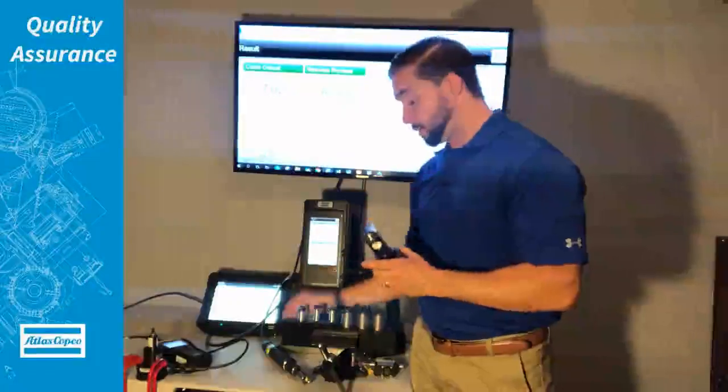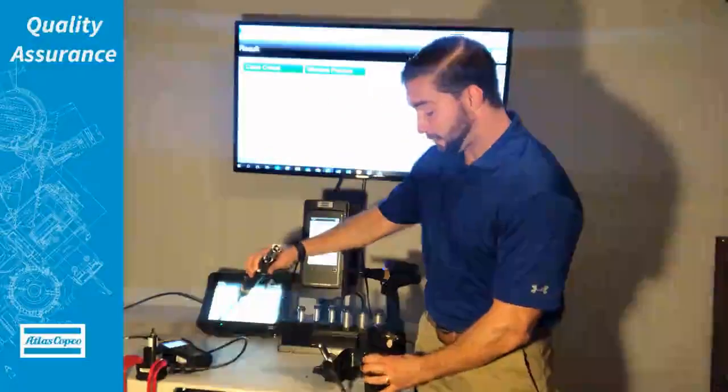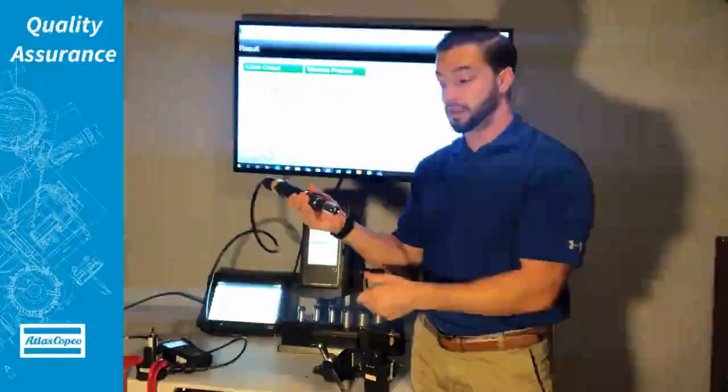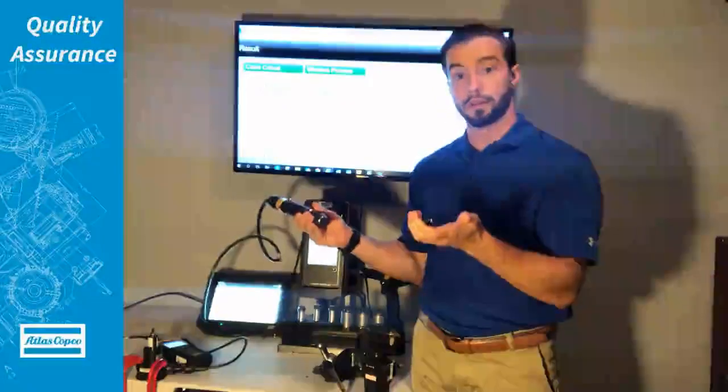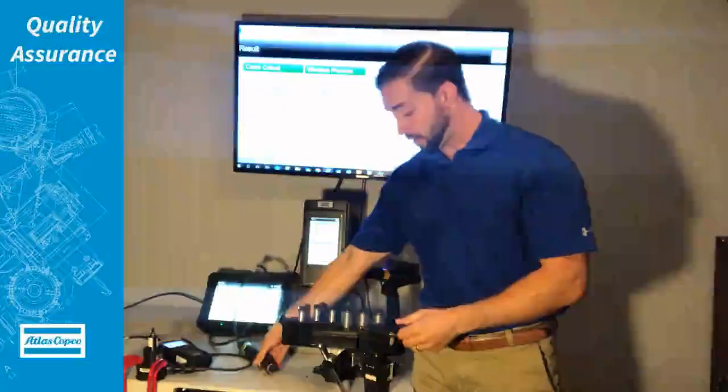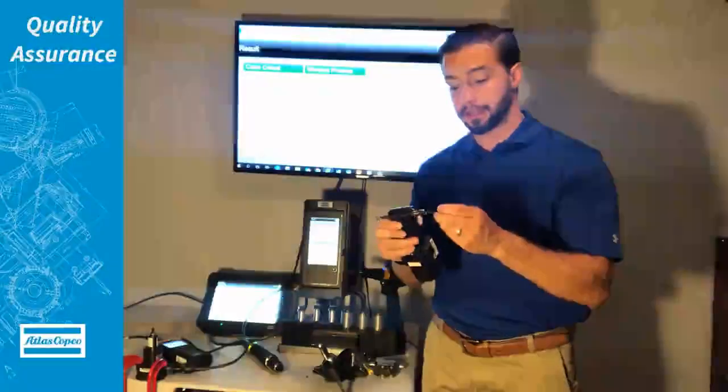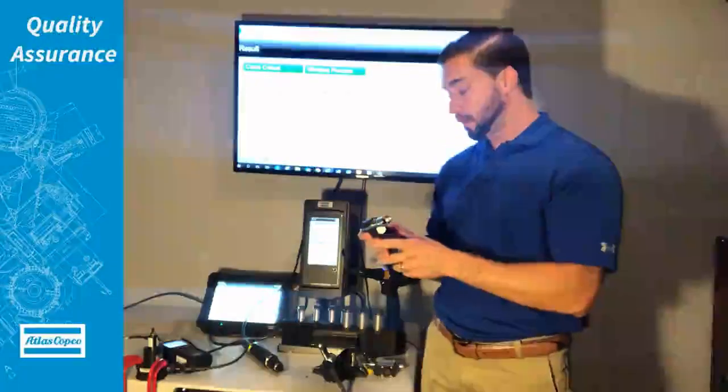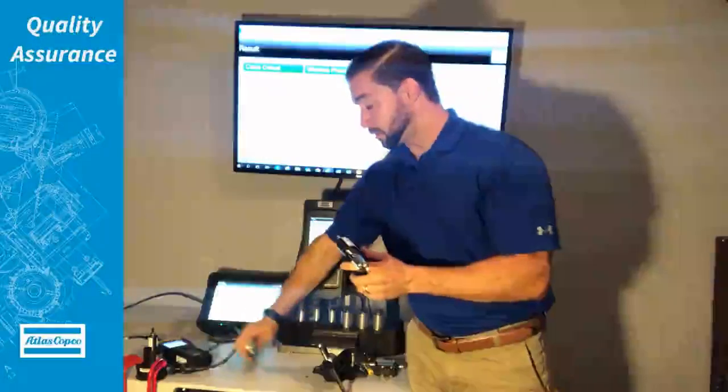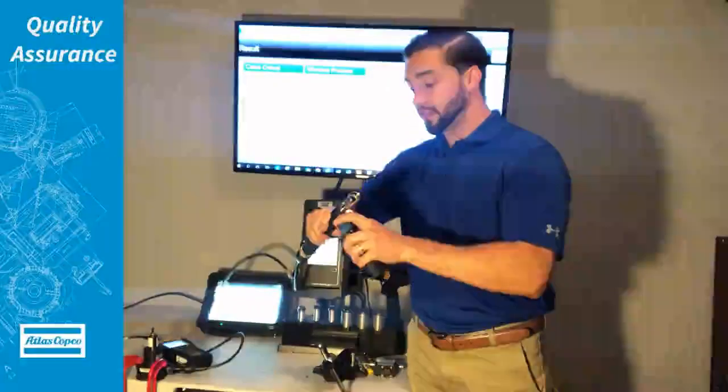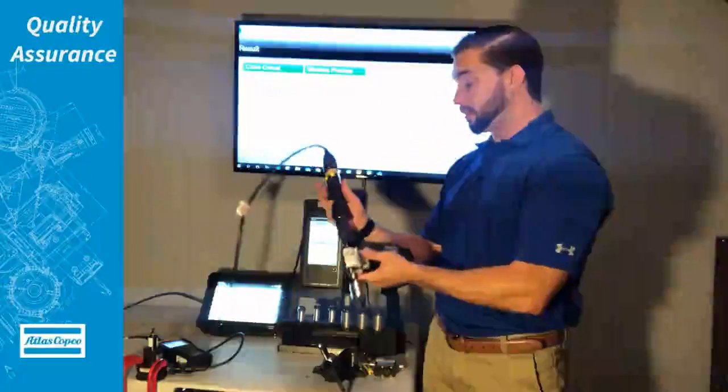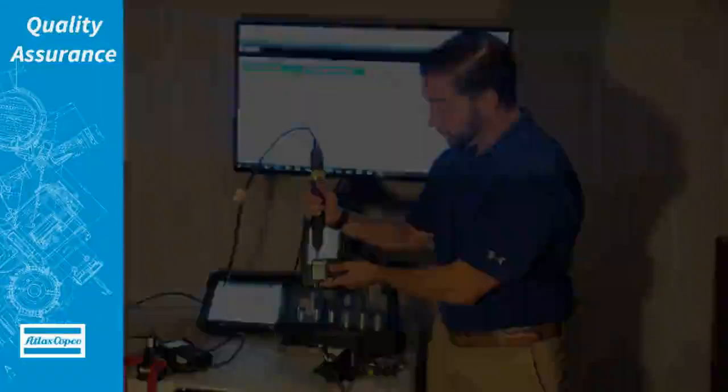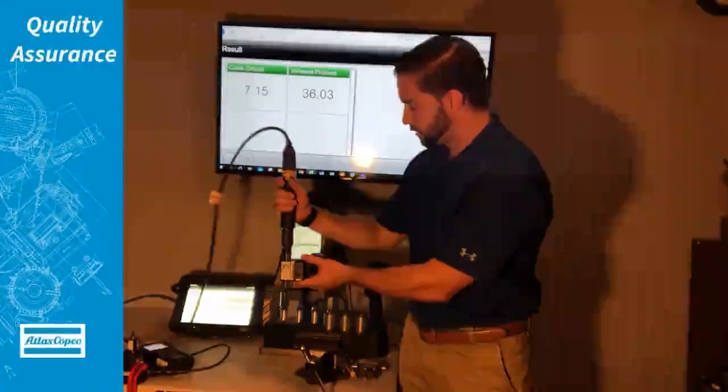What we would do is we would ask the operator to simply take out the bit that they're using or the socket. We'll add that to our inline transducer and then add the transducer to the tool. We can do all of this in just a few seconds out on the floor and now we'll do our rundowns.